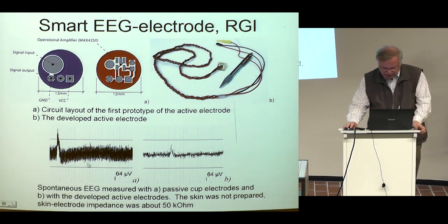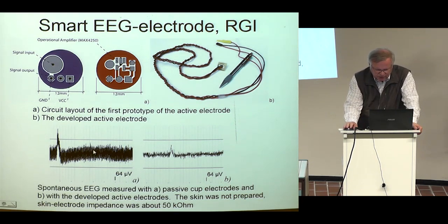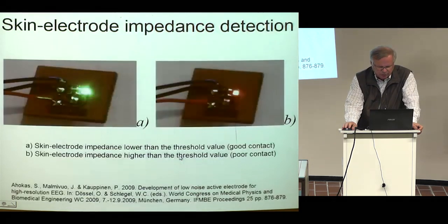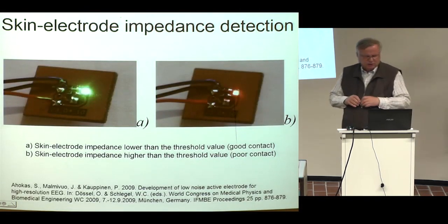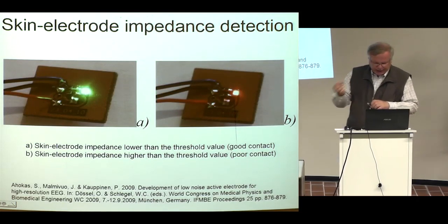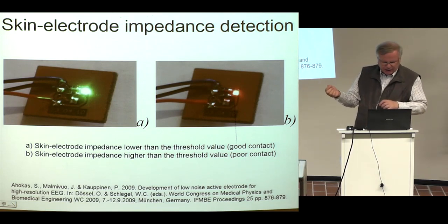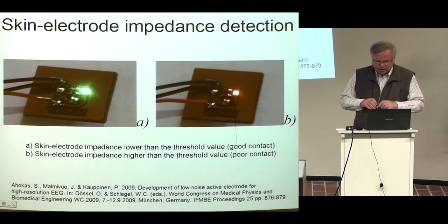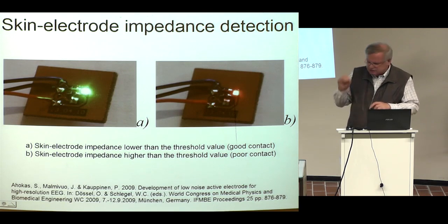Here is an example of a signal recorded with a classical electrode and with the active electrode — the noise level is much, much lower. We also added a system that detects the skin-electrode impedance: there is an LED light in the electrode indicating its color. If the impedance is good enough — low value — it shows green; if too high, it shows red. So it is a smart electrode: it is possible with the electrode itself to find what is the input impedance.